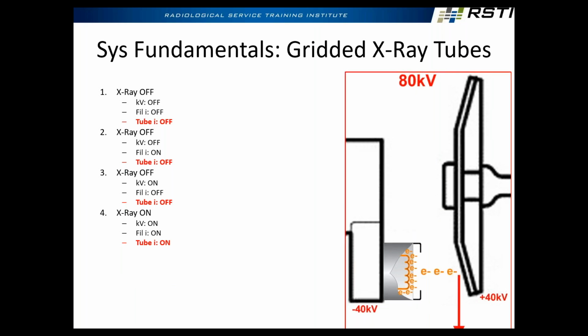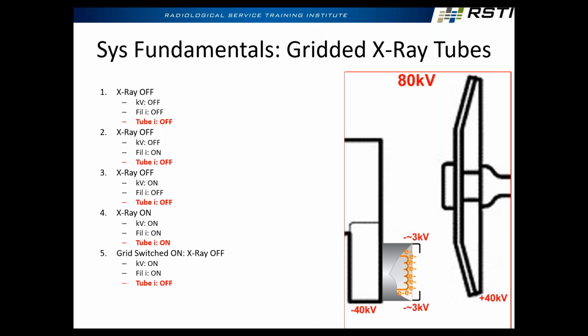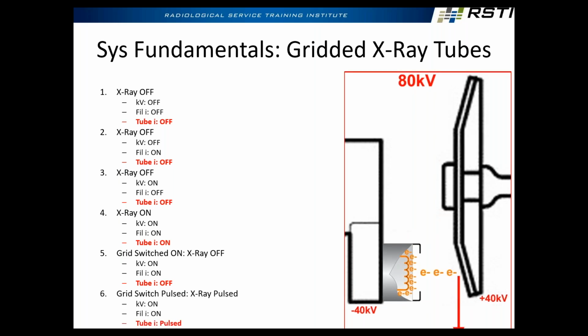So that's what this right here is showing. It's pulsing. Oh, maybe. Here. 3 kV, radiation off, radiation on. So this is called pulsed fluoro in gridded X-ray tubes, and how we're going to control any modern system. All cath labs, all CT do it like this now, and they're actually going to pulse that bias voltage to start and stop the mA. So the kV is firing the whole time.